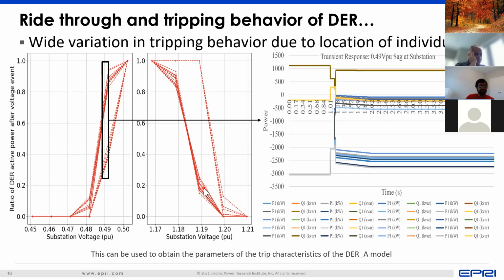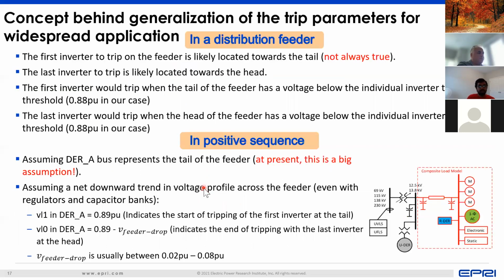So we need to take this into consideration now while we parameterize our positive sequence model. The concept that we use to parameterize the positive sequence model is to walk through how a DER would trip, wherein we say that let's say that the first inverter to trip is likely located towards the tail of the feeder, because that is where there is minimum amount of voltage control, so the voltage can vary quite a bit. The last inverter to trip is located towards the head of the feeder because that's closer towards the substation where the voltage can be a little bit more stiff.